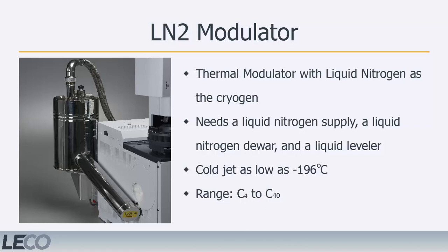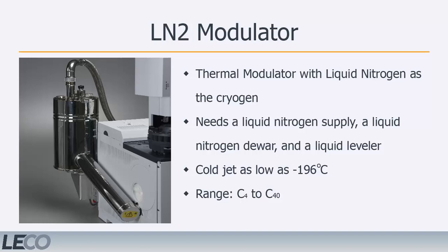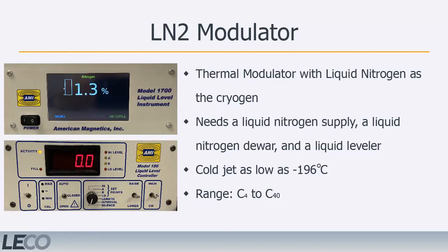The most commonly used modulator in the LECO GC×GC systems is the thermal modulator with liquid nitrogen as the cryogen. This setup employs a small liquid nitrogen dewar attached to the rear of the GC. This small dewar is usually filled with liquid nitrogen from a large, industrial-sized dewar. The filling process is controlled with a device called the liquid leveler. For the focusing portion of the modulation process, a jet of dry nitrogen gas is used. The nitrogen gas has been chilled by passing it through a coil immersed in a dewar of liquid nitrogen, or LN2.